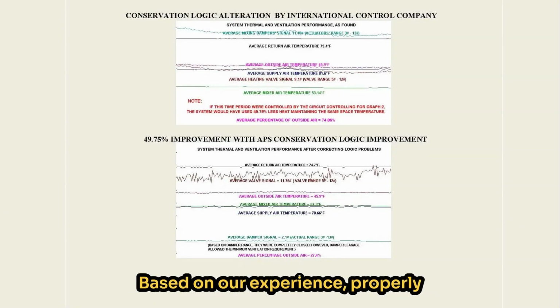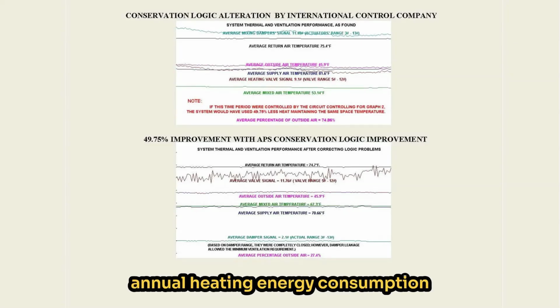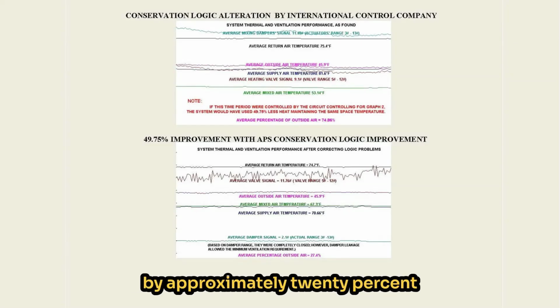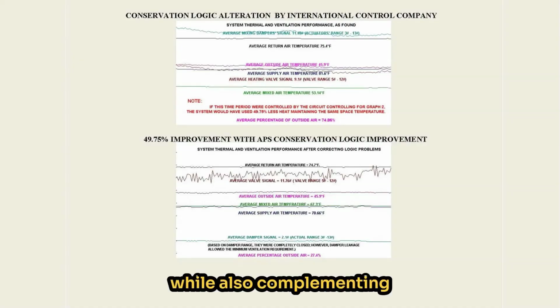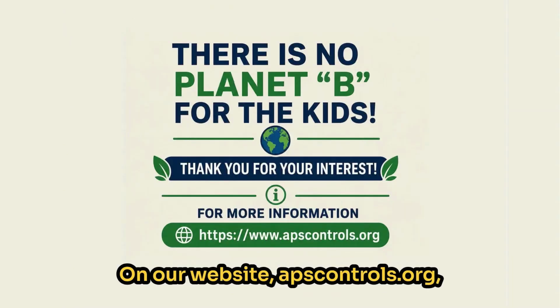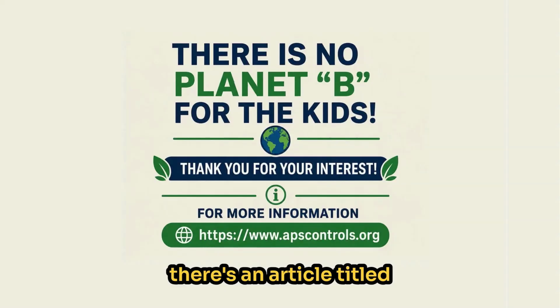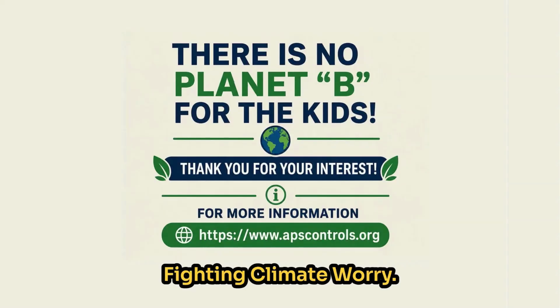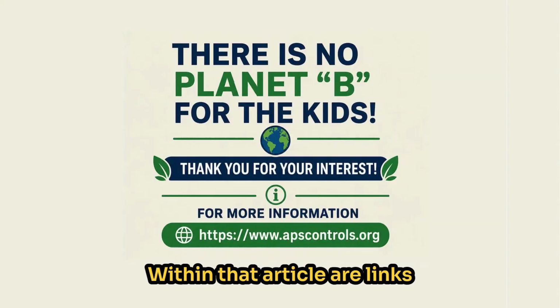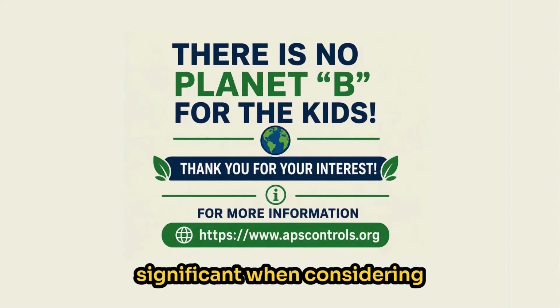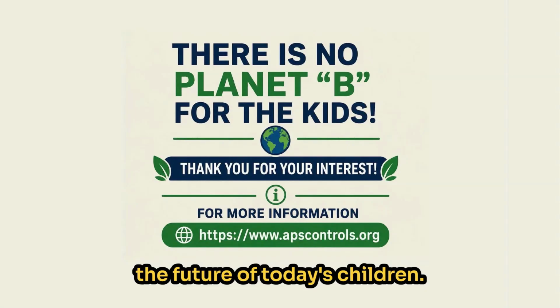Based on our experience, properly sequenced heating operation with mixed air control typically reduces annual heating energy consumption by approximately 20%, while also complementing other conservation strategies. On our website, apscontrols.org, there's an article titled Fighting Climate Worry. Within that article are links to two reports that are highly significant when considering the future of today's children.